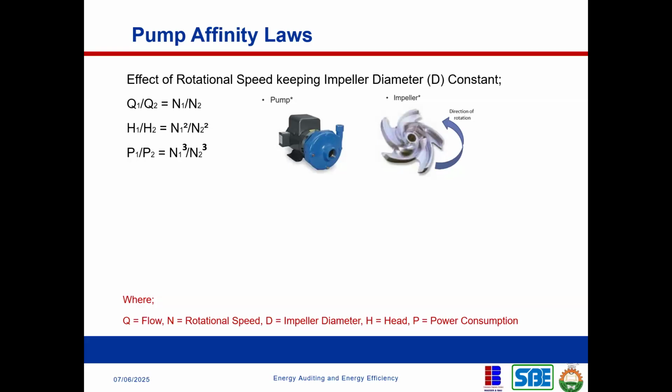So if, for example, the flow was happening at 9,000 liters per minute and you reduce this to 7,000 liters per minute, how does it affect the impeller speed? How does it affect the impeller diameter? If you need to redesign the impeller diameter, what should be the size of the impeller diameter such that you maintain an optimal efficiency? Okay, so we're going to work an example to help us understand all of this.